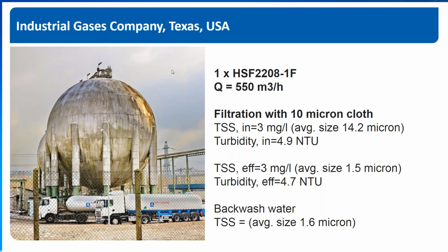Here are some case studies for cooling tower sidestream filtration. First one is an industrial gas company where we have one disc filter. At this site, it's filtered with a 10 micron cloth. The TSS coming in is around 3 milligrams per liter, and the TSS coming out is also around 3 milligrams per liter.